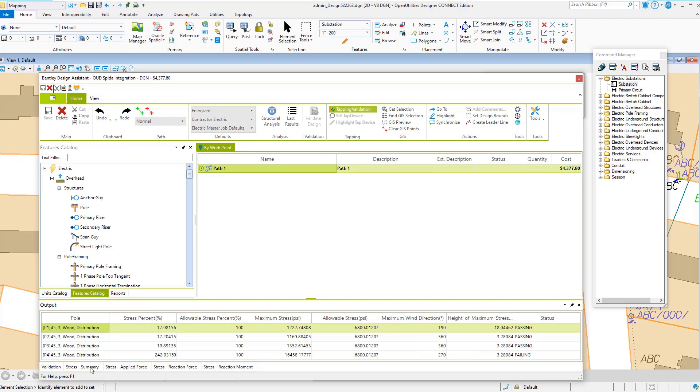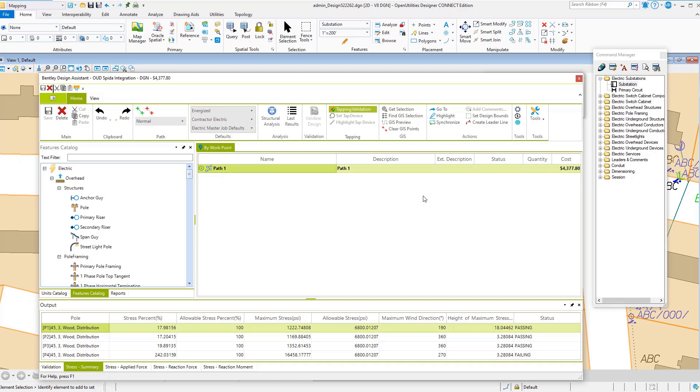I'll look at our stress summary: one is 19% passing, two is 17% passing, three is 19% passing, four is 242% stress - it's failing. So why don't we take a look at Spida Calc and see what's happening.